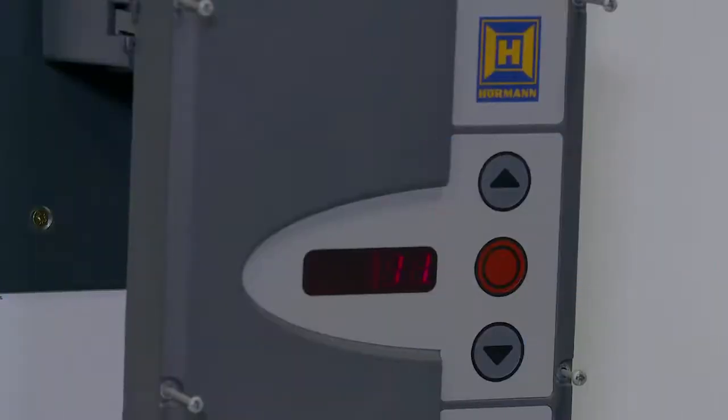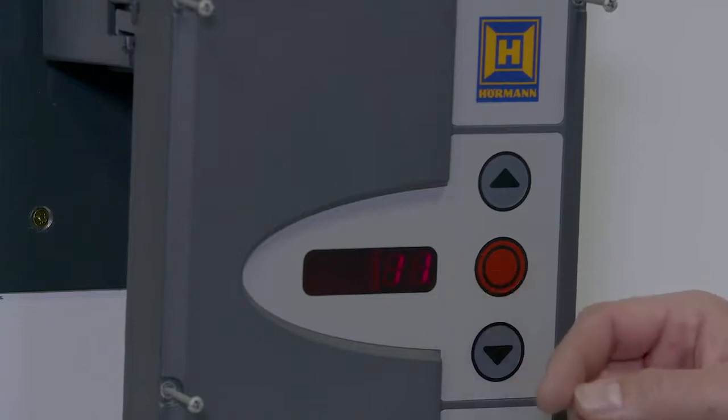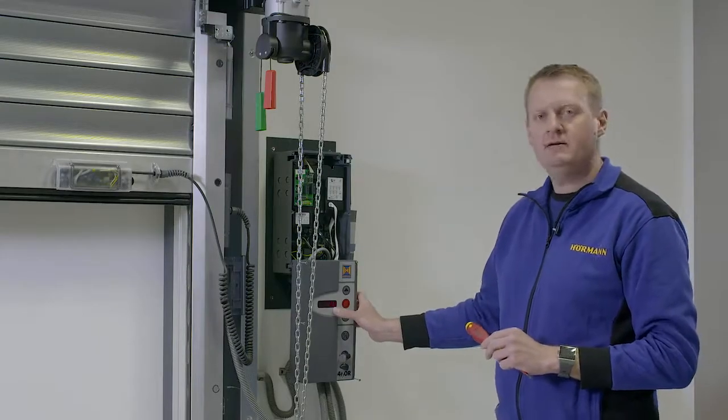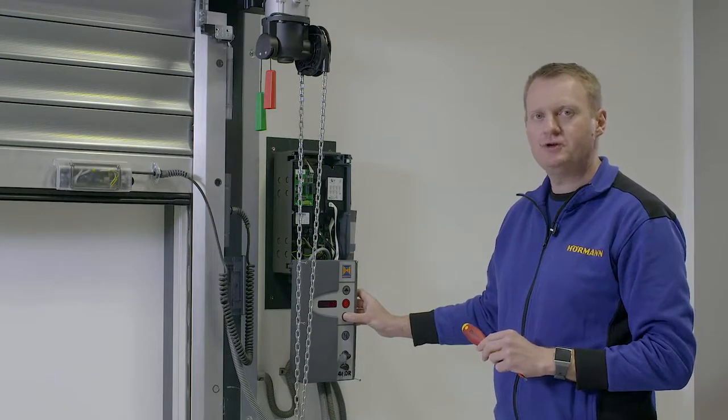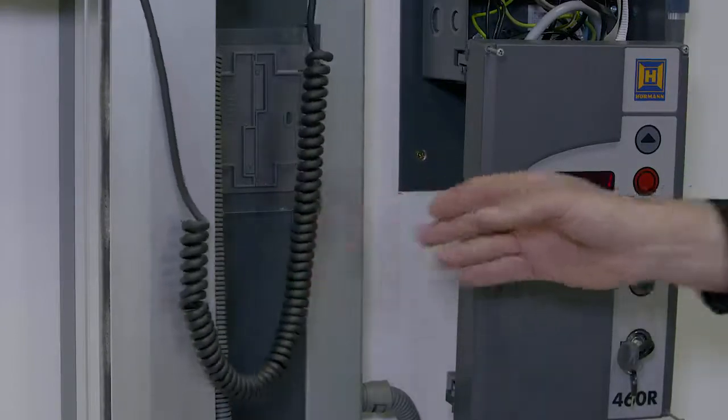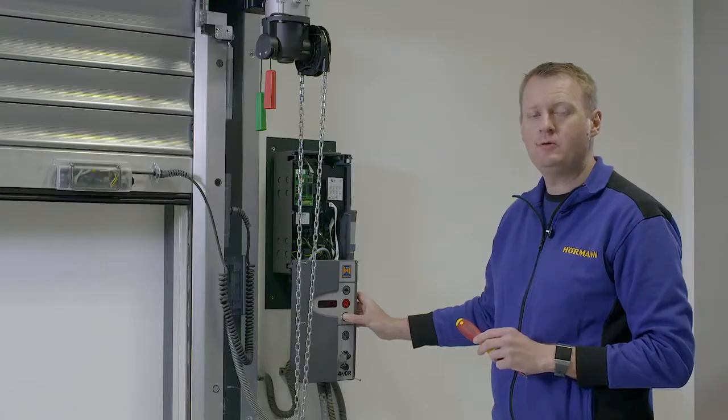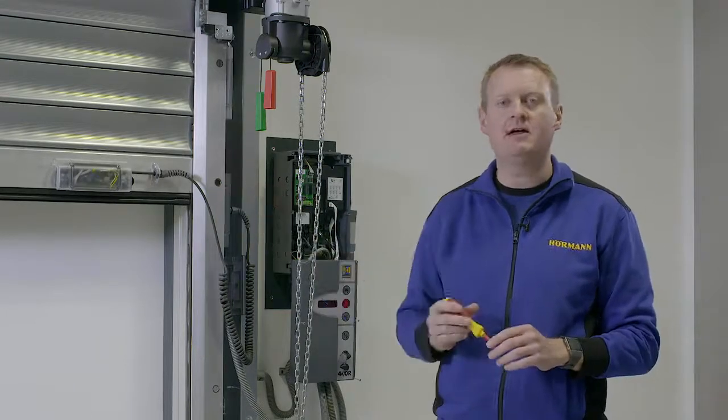A common fault code is code 11. This is the infrared sending receiver in the bottom rail. With 11 showing on the display, press and hold the down button. If the door doesn't close, the fault will probably lie with the curly cable. If the door does close on dead man control, the fault will probably be with the infrared sending receiver in the rubber.